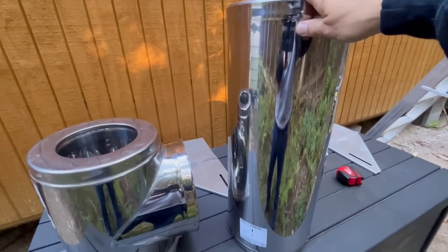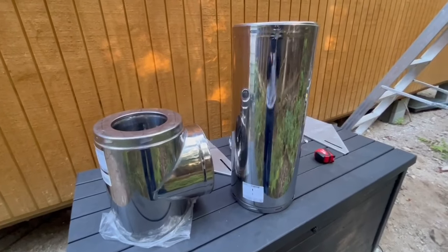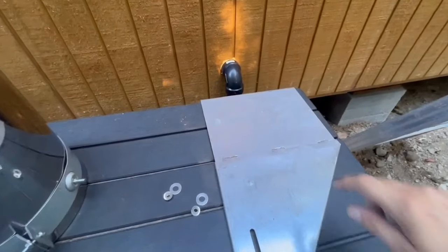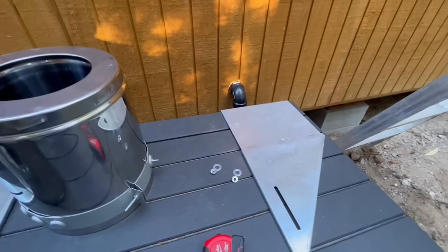Fast forward one week — back at the cabin, back to try to finish this fireplace slash chimney install. Had the boys in the shop modify the brackets again for me. I didn't realize that the size you need is only partially dictated by the distance you need to come off the wall — you need to be two inches from combustibles — but the main factor is the piece of pipe that fits through the thimble. Because I'm using this two-foot piece, I needed to come off the wall about another four or five inches. The brackets have been modified with this piece, so hopefully this will work this time.